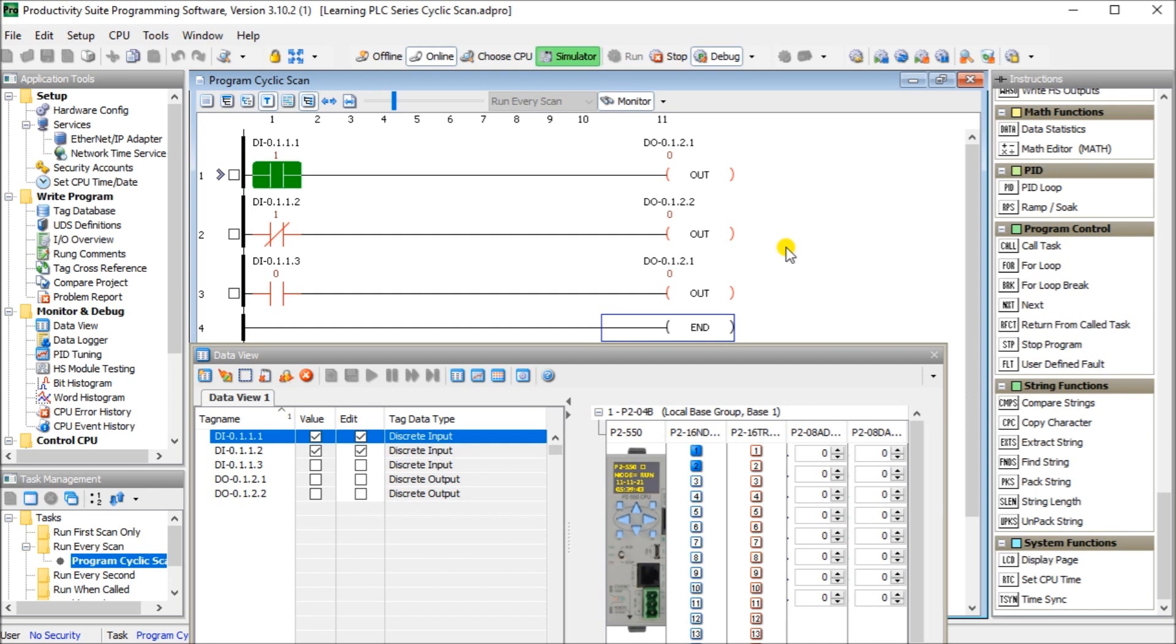Everything we've talked about so far will use a synchronous PLC scan. Controllers like Allen Bradley Compact Logic using the RSLogix 5000 software use asynchronous IO scan. This means that updating of IO will happen whenever it can. An asynchronous IO scan, you typically will only use the actual IO reference once in your program. Most programmers of these systems will transfer the IO to internal memory first, then they will use the internal memory in the program code. This will now act as a synchronous predictable scan.